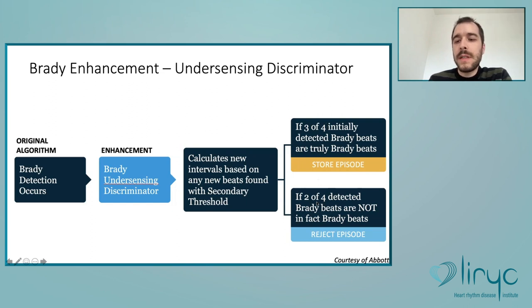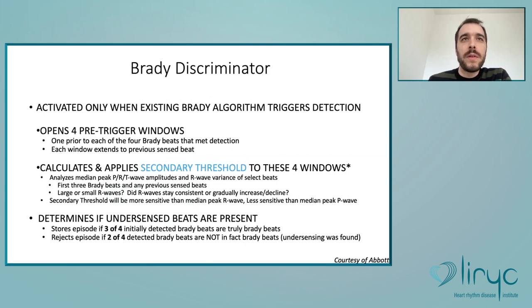Or if 2 out of 4 detected Brady beats are not in fact Brady beats, then it will reject the episode. So this Brady discriminator will be activated only when there is a trigger for detection of bradycardia. It will open 4 pre-trigger windows, 1 prior to each of the 4 Brady beats that met the criteria for the detection.